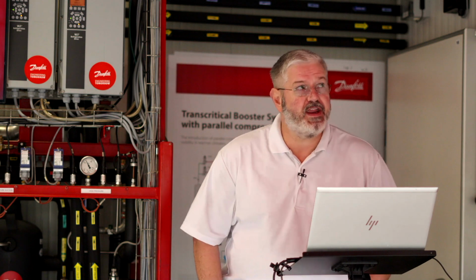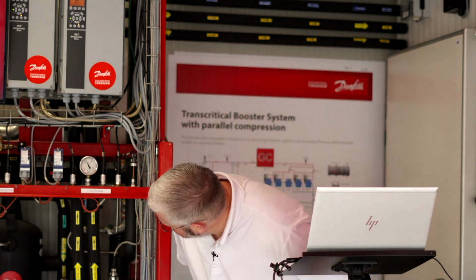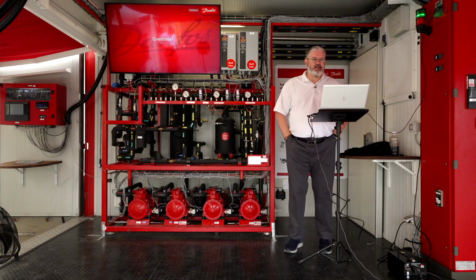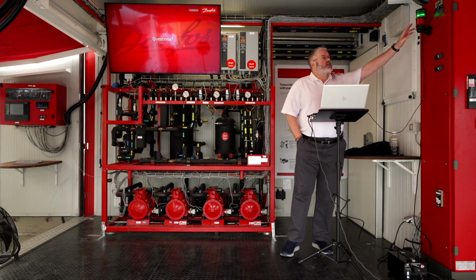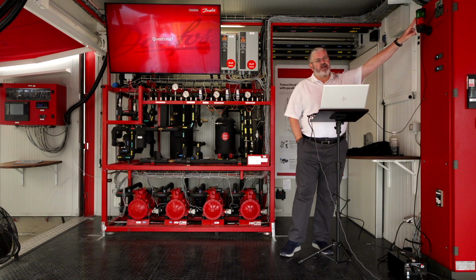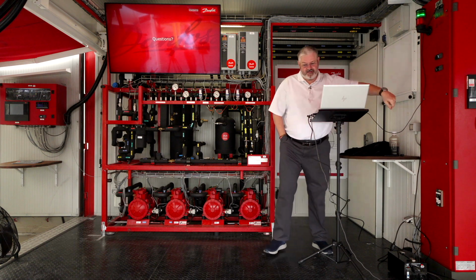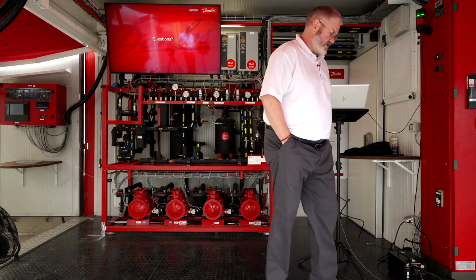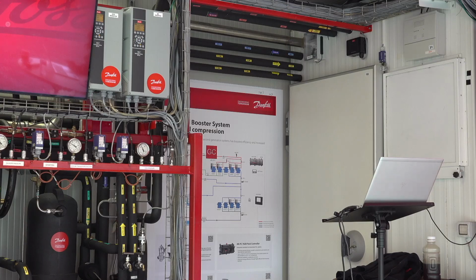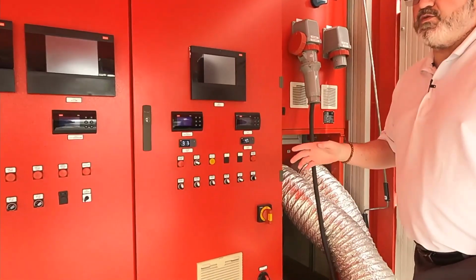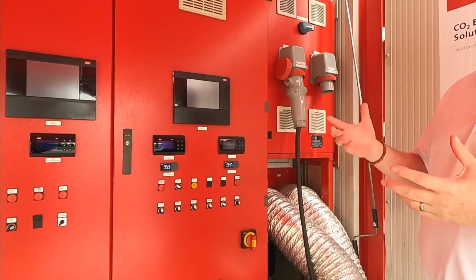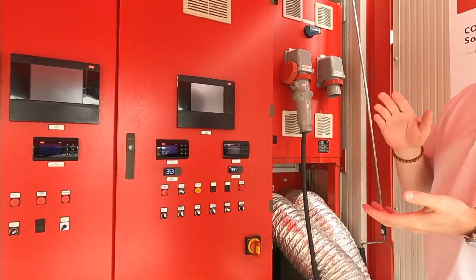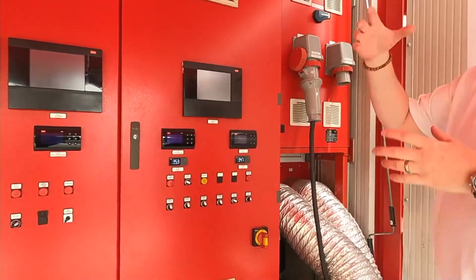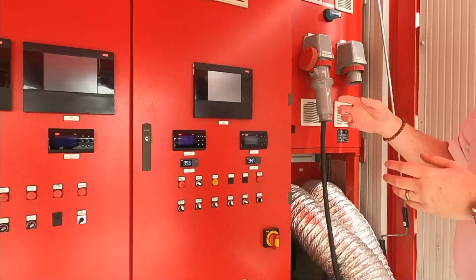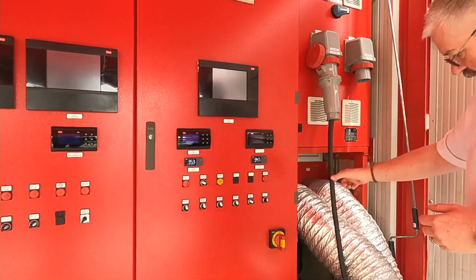Okay, so the red and green lights on the flash tank. I don't see the red and green lights on the flash tank. If we're talking about what I'm pointing to here, it's tied to a switch. Can we get a close-up? That's actually, I've never been asked that. Great question. So here, with CO₂, one of the safety considerations with the high pressure, you have pressure relief valves on your suction header, your liquid line, your discharge line. They all go to a common header via flexible hose, and then that is piped over and outside of the store.